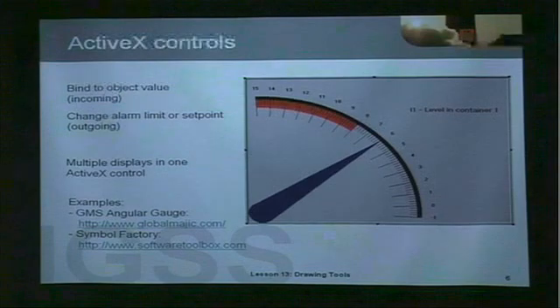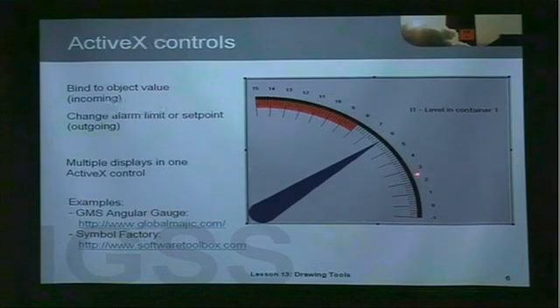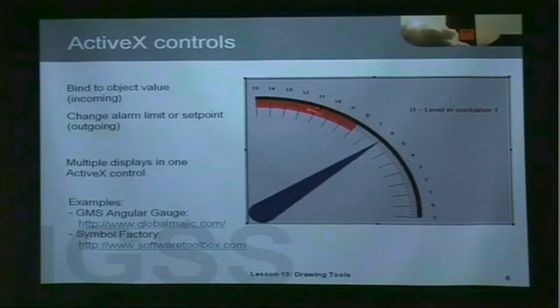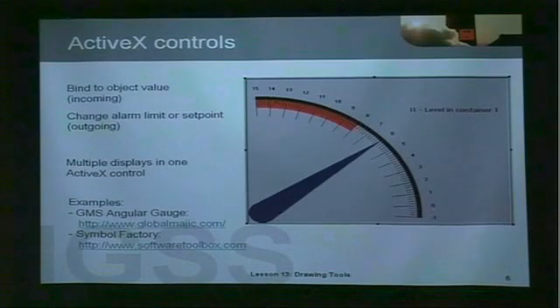You can embed ActiveX controls in IGSS — there are lots of them on the internet. We have purchased, for example, the GMS Angular gauge from globalmajic.com, which is the one you see here on the slide. It allows you to bind the needle to the object value of an analog object, as I've done here with my level meter. I can also show the alarm range — from 8 to 15 here, that's the high alarm range. You can also allow the user to change the alarm limit or set point from the needle, and in fact you will have multiple displays inside this ActiveX control. For further information, please visit the web addresses shown here.